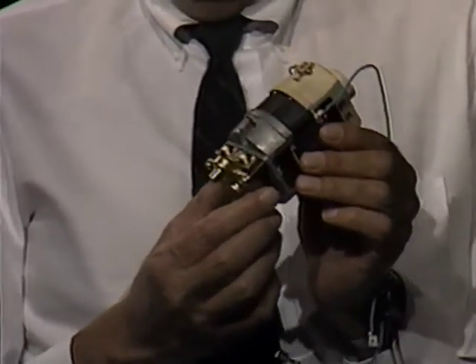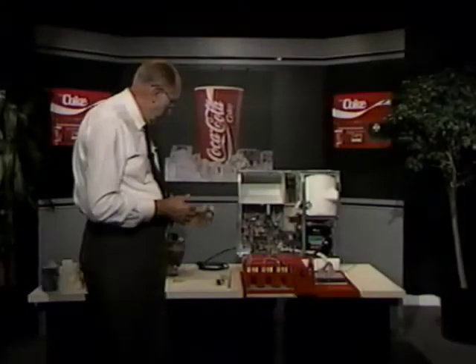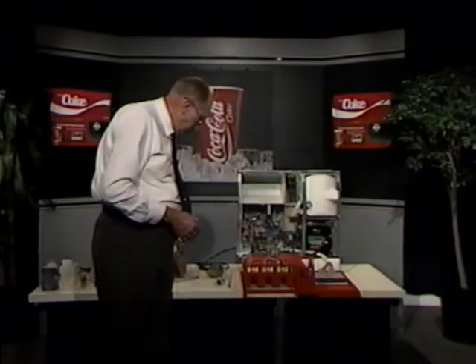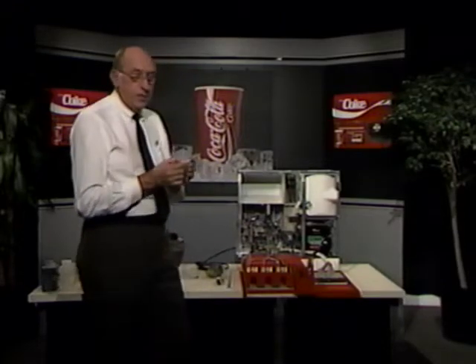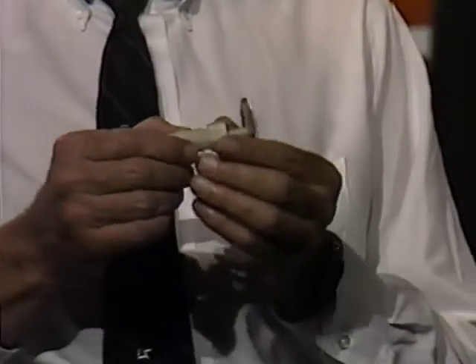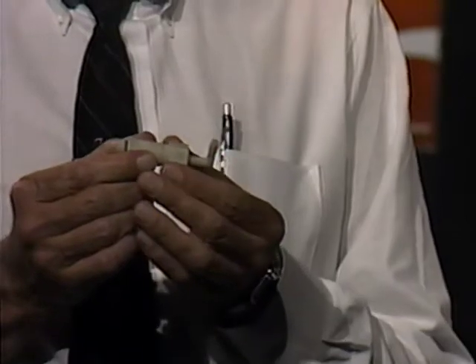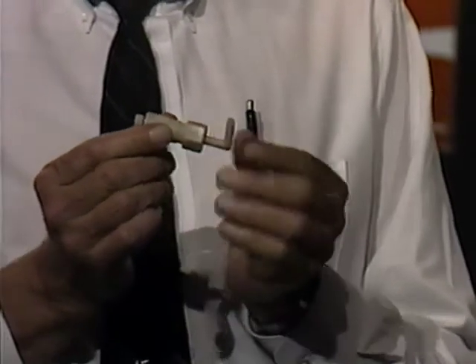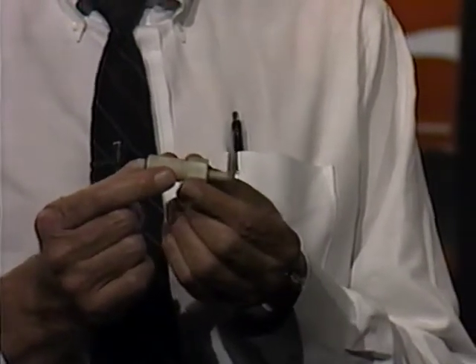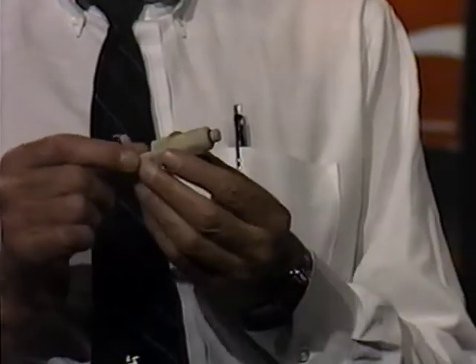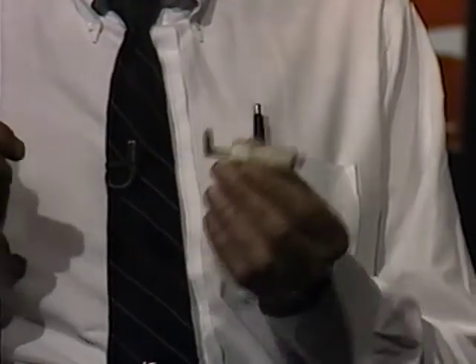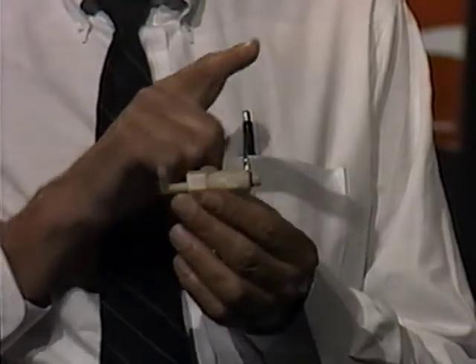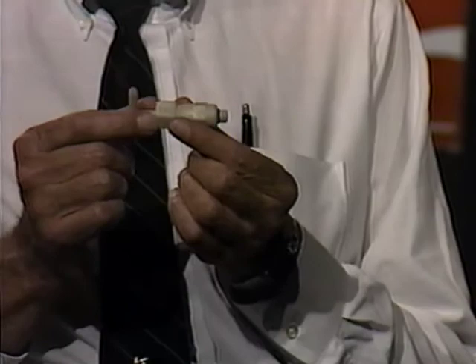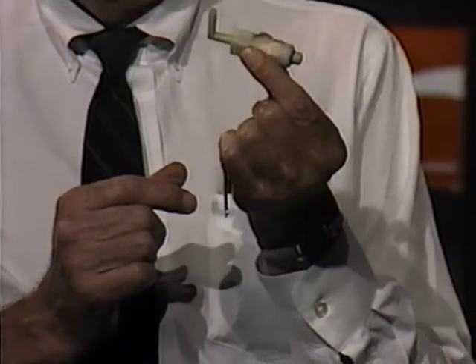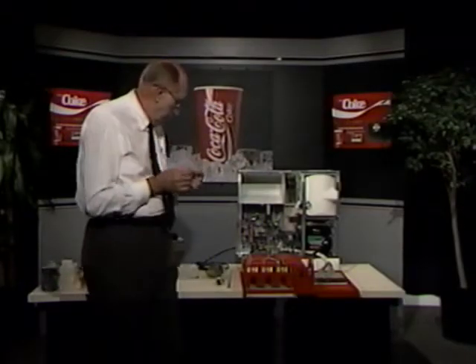Water coming out of the pump goes through a double check valve. The double check valve prevents backflow of the water or backflow of CO2 gas into the system because the carbonator has 75 pounds pressure, and if there were no double check valve in it, it would push water and CO2 gas right through the pump back into the water line. So the double check valve is a backflow preventer, keeping CO2 gas from backing into the water line.